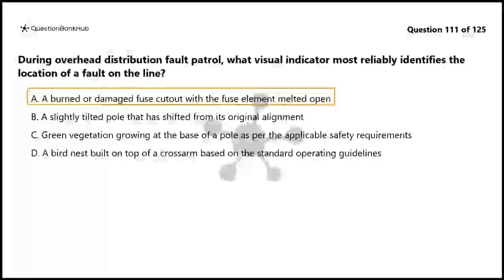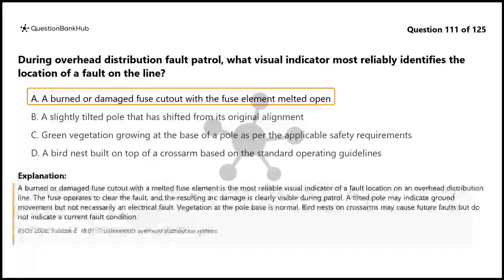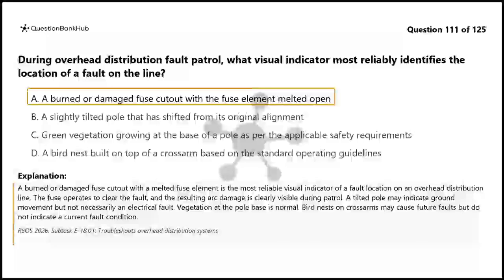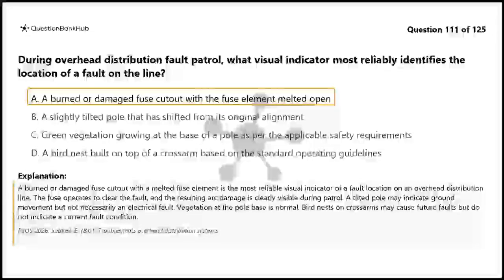The correct answer is A. A burned or damaged fuse cutout with a melted fuse element is the most reliable visual indicator of a fault location on an overhead distribution line. The fuse operates to clear the fault, and the resulting arc damage is clearly visible during patrol. A tilted pole may indicate ground movement but not necessarily an electrical fault. Vegetation at the pole base is normal. Bird nests on crossarms may cause future faults but do not indicate a current fault condition.